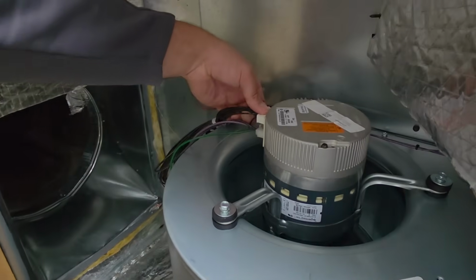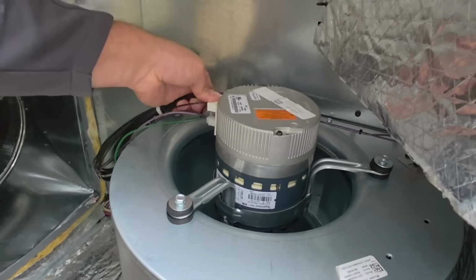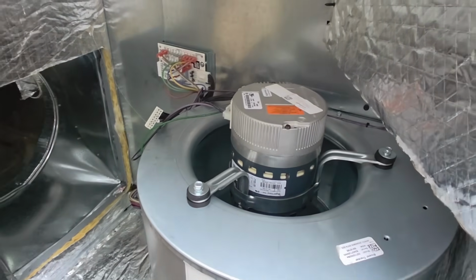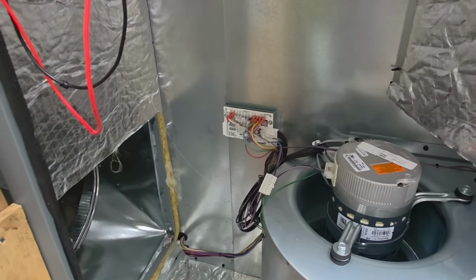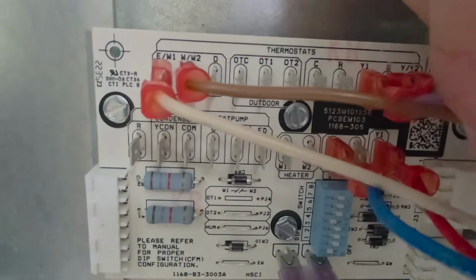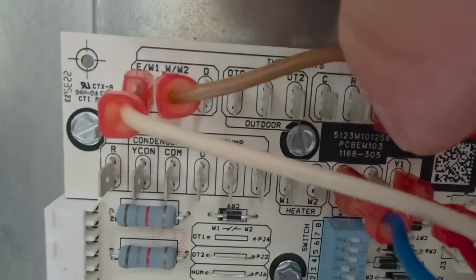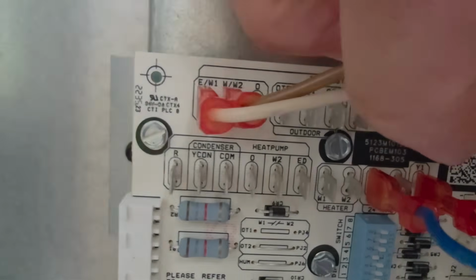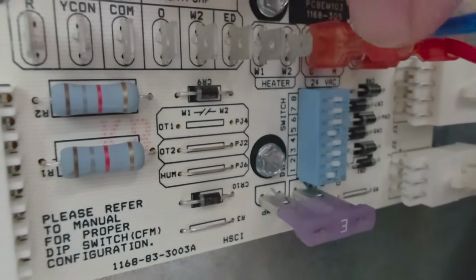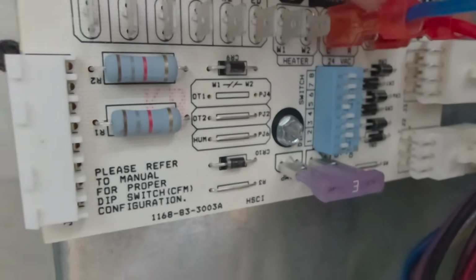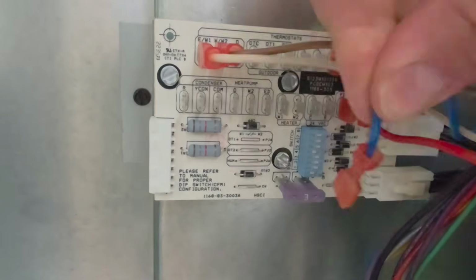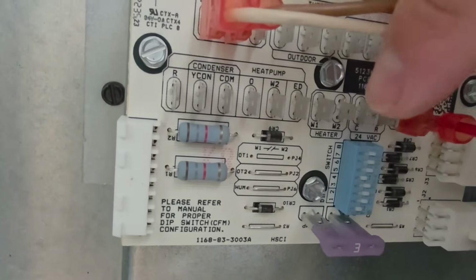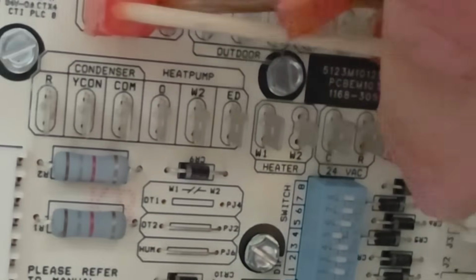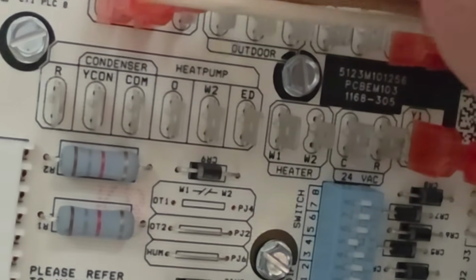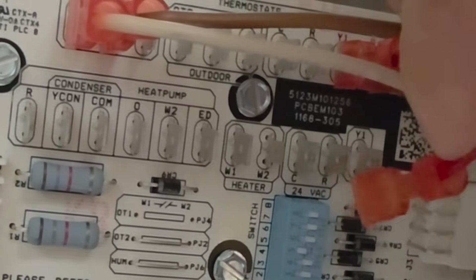So if we take this off, so that this motor will not run, and we go into the board where these wires land, you see that Y1? There's a red wire there. Where is it supposed to be? You see this where it says 24 volt? Let me take this wire off so you can see better. See that where it says C and R? All right, simple mistake. Someone landed the wire on the wrong terminal.